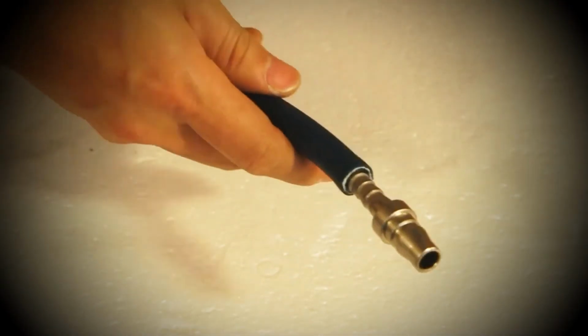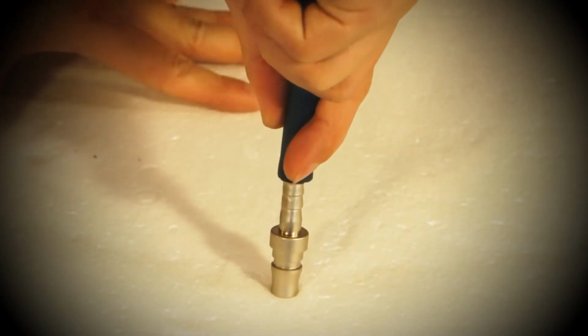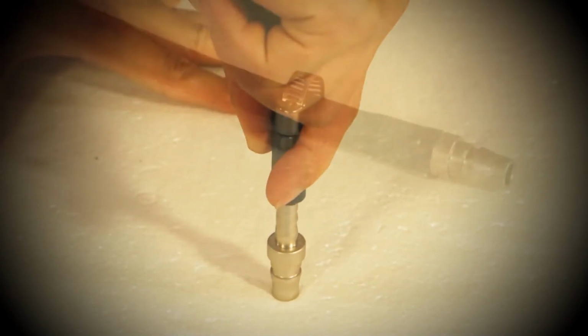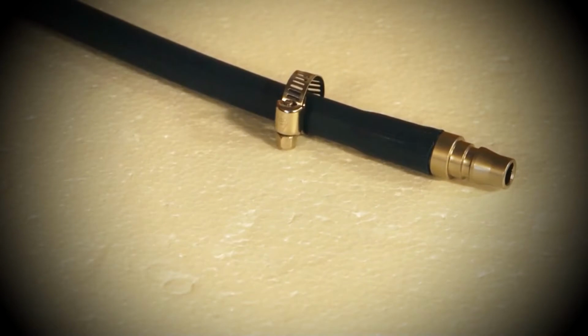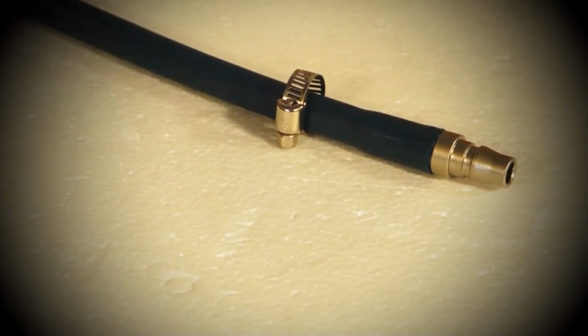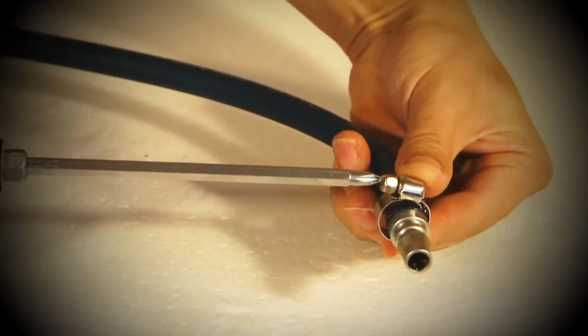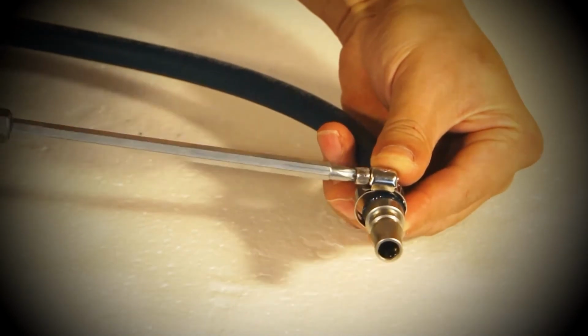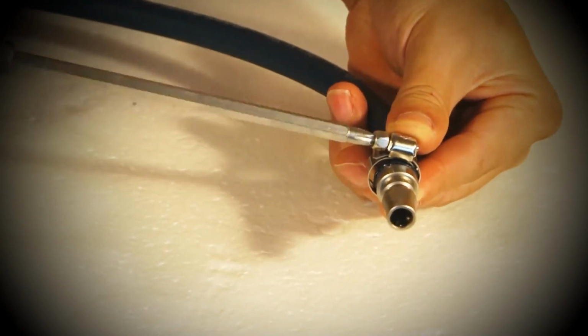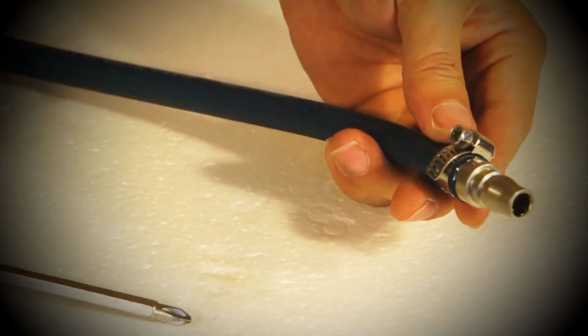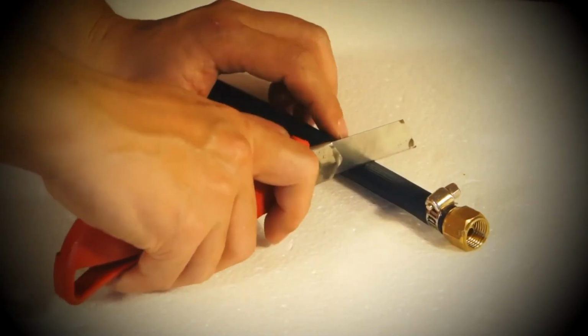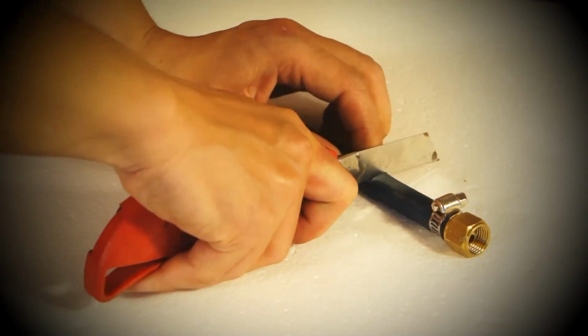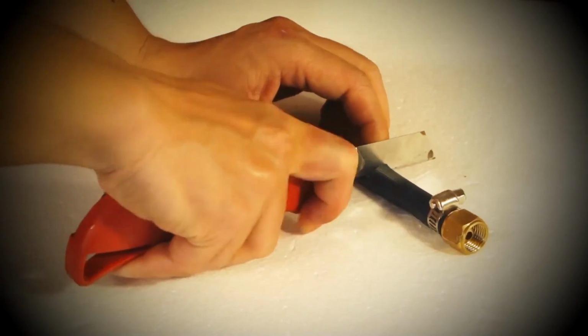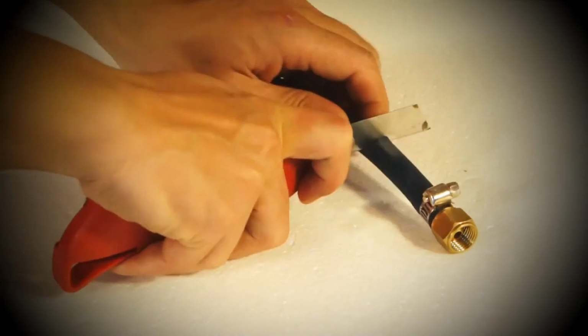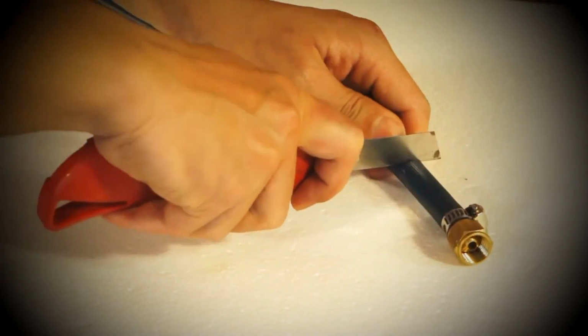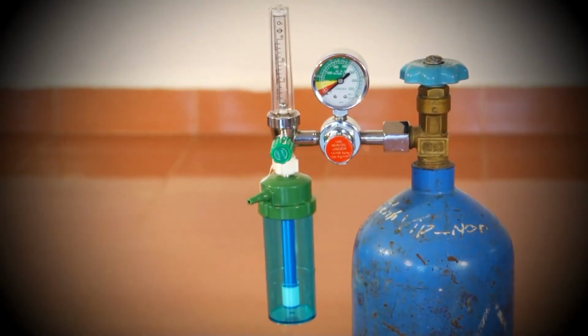It will require some force. If needed, place the connector on a hard surface and push the tube onto it. Once the connector is in place, slide the ring clamp to the edge of the hose and use a Phillips head screwdriver to tighten the clamp. If none of the connectors fit, you can clamp the hose directly to the oxygen source. It's a suboptimal solution and not recommended unless there is really no other choice.